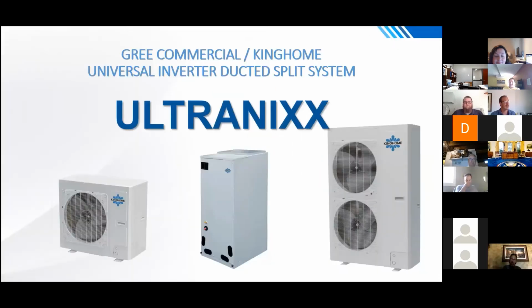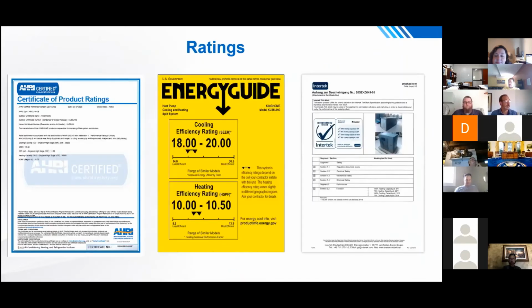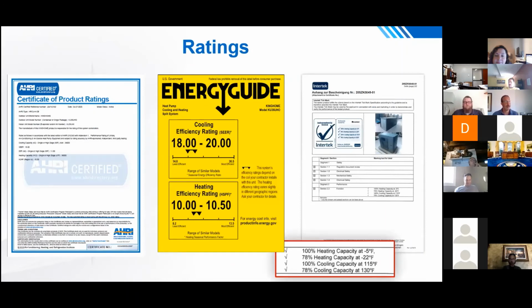All right, enough silliness, moving back onto the product. So here's Gree's lineup, at least as it comes to this particular offering. The smaller and the larger outdoor unit and what looks to be an indoor furnace, but it's an indoor air handler. So yes, maybe you're not familiar with buying stuff directly through China, but the stuff that you're used to seeing is on there. So like at home, your air handler probably has a big yellow sleeve with a piece of paper in it that says what the energy guide is. AHRI has certified all these products, and Intertek has tested and agreed that the output heating capacities that Gree is marketing match up with what their catalog literature says. So that's all good stuff that we're familiar with.